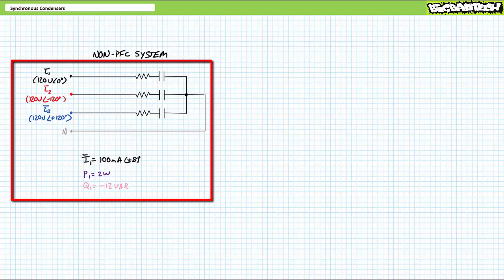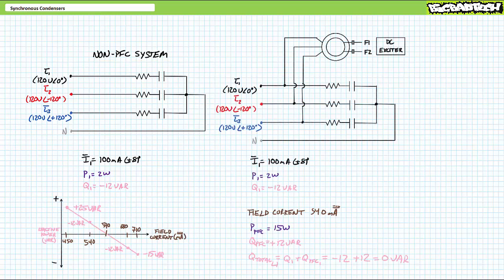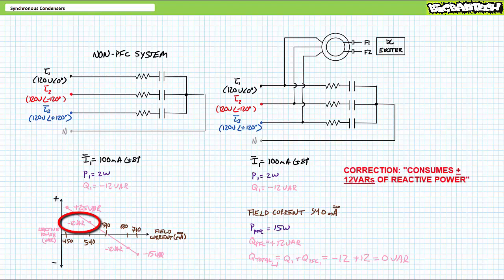This is well inside the correction range of this particular device. I would suspect we need to slightly underexcite the rotor to consume an equivalent amount of positive reactive power. When we bring the synchronous condenser in parallel to the load, each load continues to draw the same current and supplies the same negative 12 VARs of reactive power per phase as previously. When we decrease field current to approximately 540 mA DC and underexcite the rotor, each winding of the synchronous condenser consumes roughly 15 watts of real power for friction, but in this underexcited state consumes positive 12 VARs of reactive power — equal in magnitude yet of opposite polarity to the load.